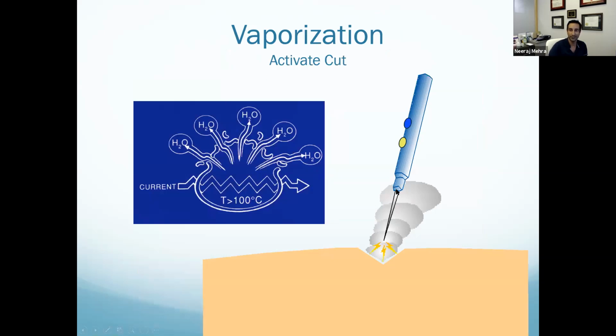When you vaporize something, you're going from maybe 5 millimeters to 4 millimeters, and the tip of your instrument can even be just a few millimeters, so this gap is almost imperceptible. But the energy is still having to flow across that gap, and it's flowing at a high current density. When you have a huge amount of energy flowing through something with an extremely high current density, you have a huge amount of force going through that, and that force just causes the tissues to vaporize. Whereas if you touch the tissue, all of a sudden you've dropped your current density, and that causes the tissue, instead of completely vaporizing, to dry out, what we call desiccate.